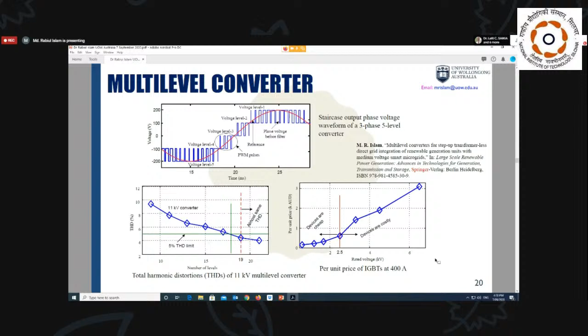So maybe the question you may have is, it requires more switches or switching components, which may increase the cost. Actually, it is not true, because multi-level converters give you the chance to use low rated devices rather than high voltage rated devices. If you search the website or somewhere, you can easily find that lower rated devices are much more mature and cheaper than high voltage rated devices. So therefore, although the number of components is increased, the total cost is still comparable with existing technology.